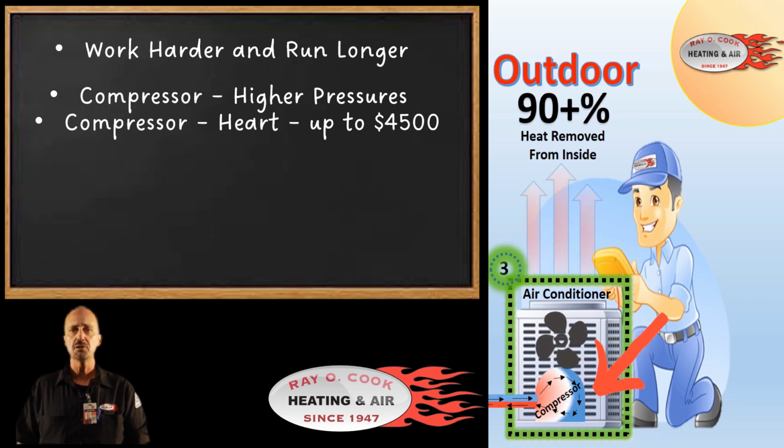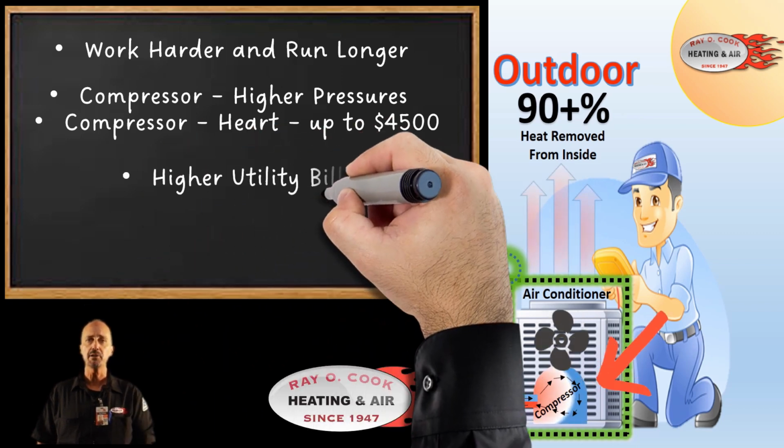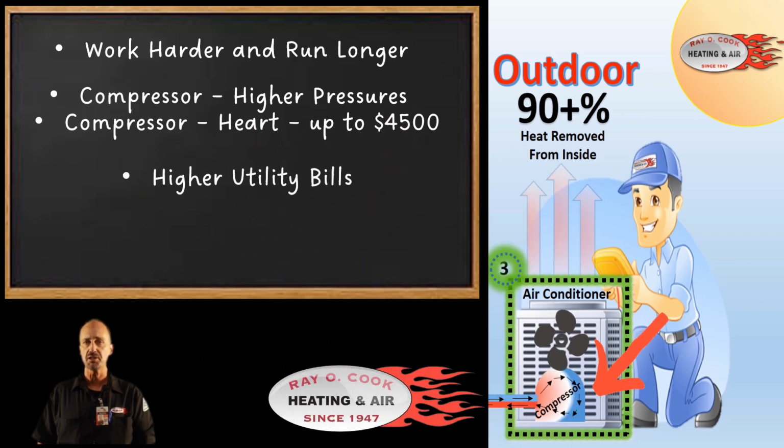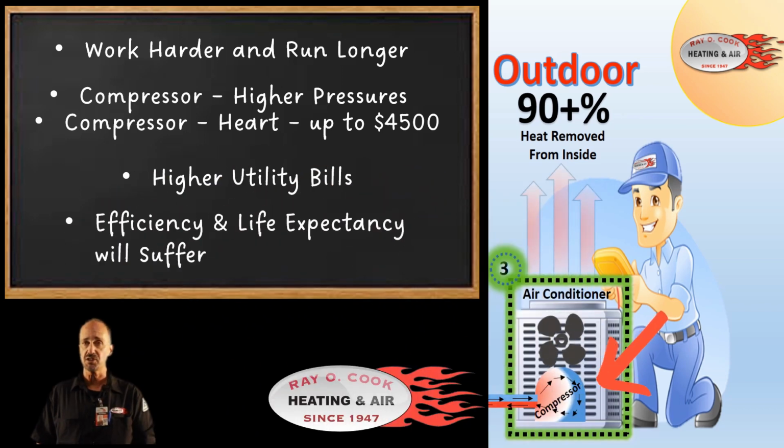Allowing a compressor to operate and run for prolonged periods under high pressure situations due to a dirty outdoor coil will only shorten its life. Additionally, a higher utility bill is a result of a compressor that is operating under higher pressures due to a dirty outdoor coil. Although an air conditioning system will work and function with dirty outdoor coils, efficiency and life expectancy will suffer.